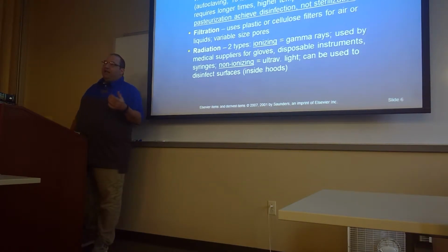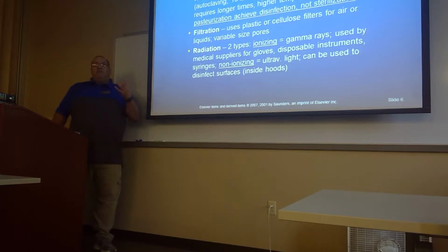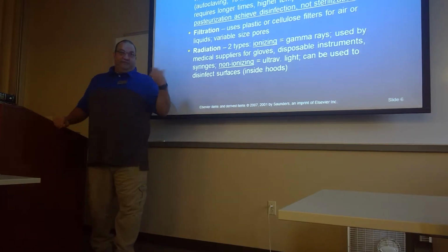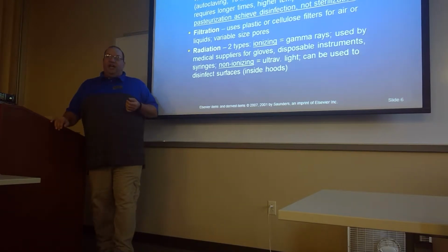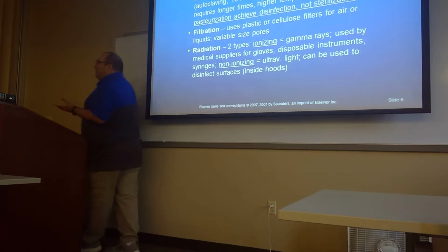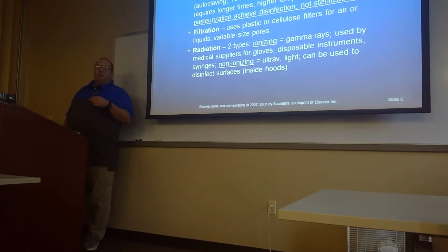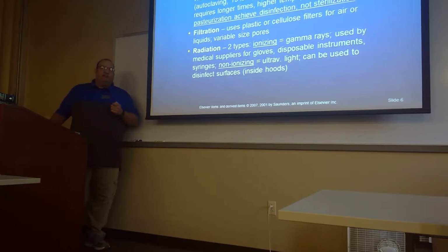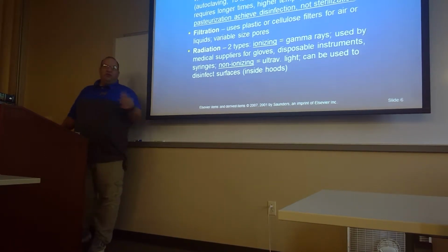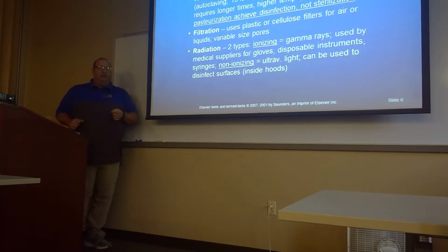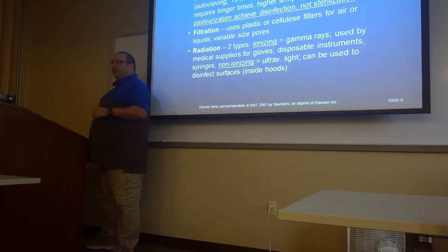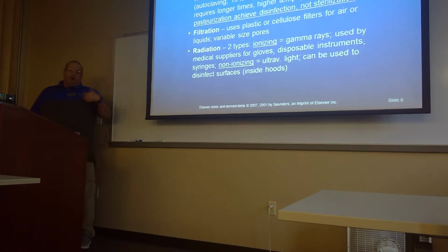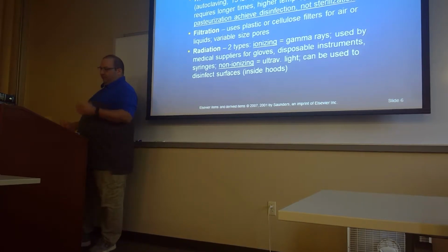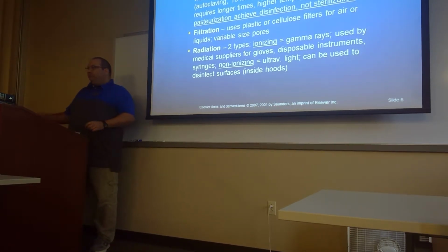Since infections and TB and stuff like that is so prevalent in prisons, when I worked at the prison, the convicts used to complain because they know the regulations. UV lights have to be present. It was one of their funnest games to break the UV lights. And they were always griping because there were no UV lights. We put them inside the ductwork of the heaters and air conditioners. They were up in the ceiling like 20 feet back in the ductwork. So all the air coming in had been exposed to UV light, and it was not a place where the convicts could break it. So that would make our life miserable, because you're mandated by law, as soon as it's broken, you have to replace it. Well, eventually, you're going to run out of UV bulbs, because they'll break them every 5 minutes. They have nothing better to do. They're convicts. They have to entertain themselves somewhere.